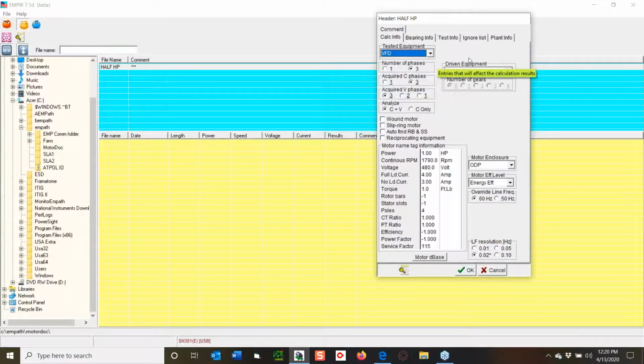So it's a VFD grade motor. Let's see, we have 0.5 horsepower. It is 1700 RPM - that's weird - 460 volt, 1.8 amp, and so we're going to over-amp it. No load current, we're going to just say 0.1, just so I don't have any problems.